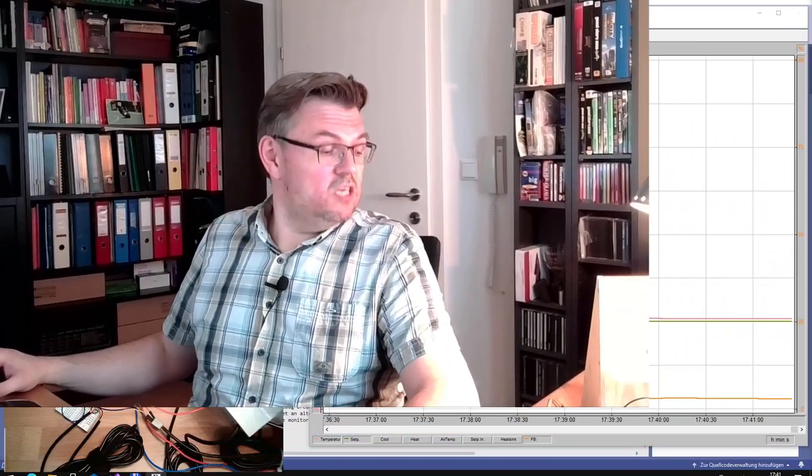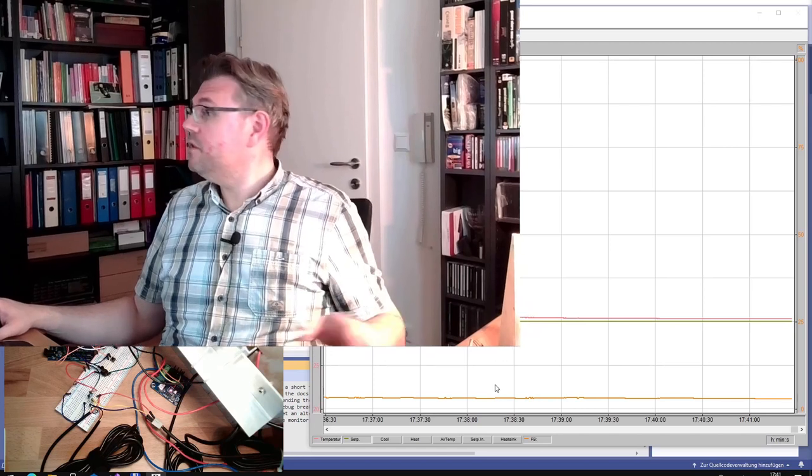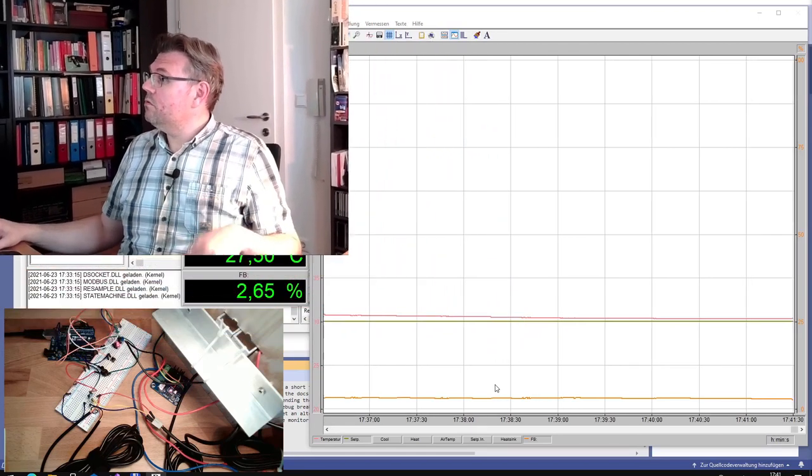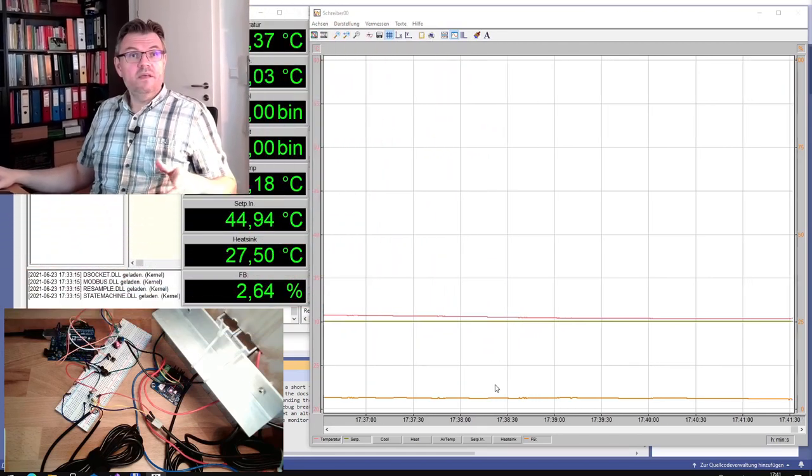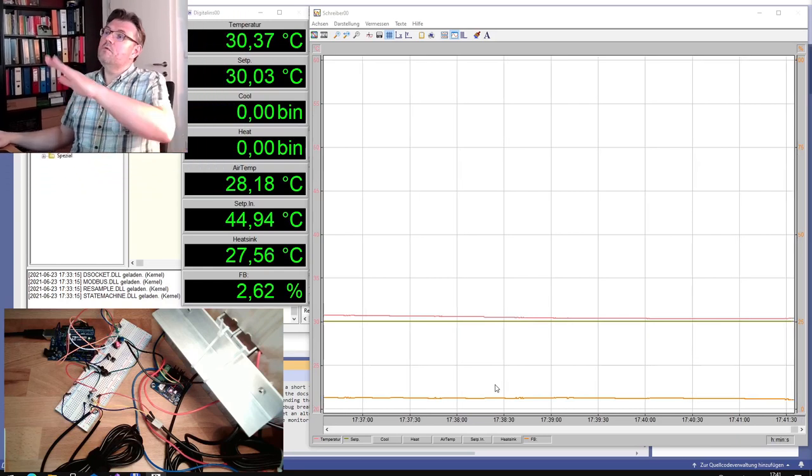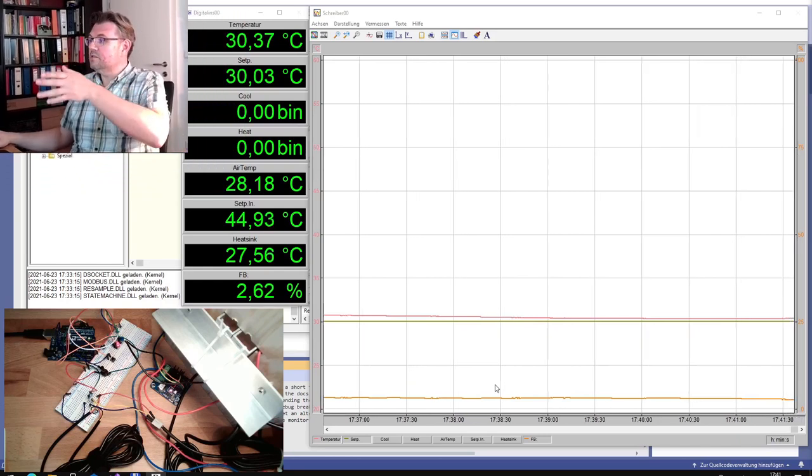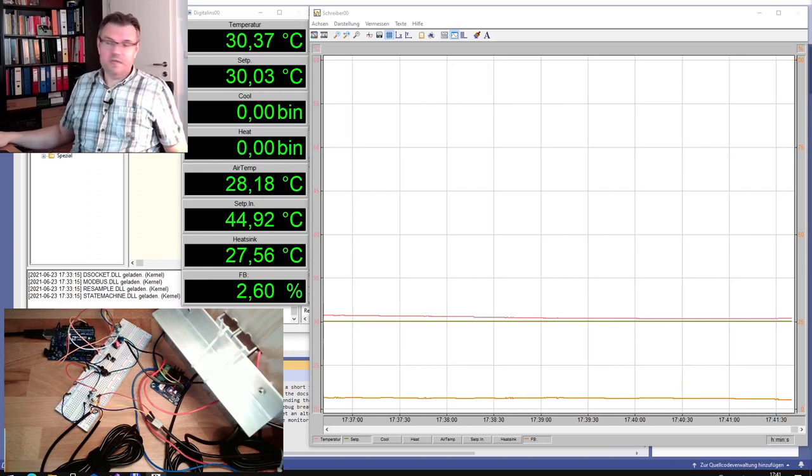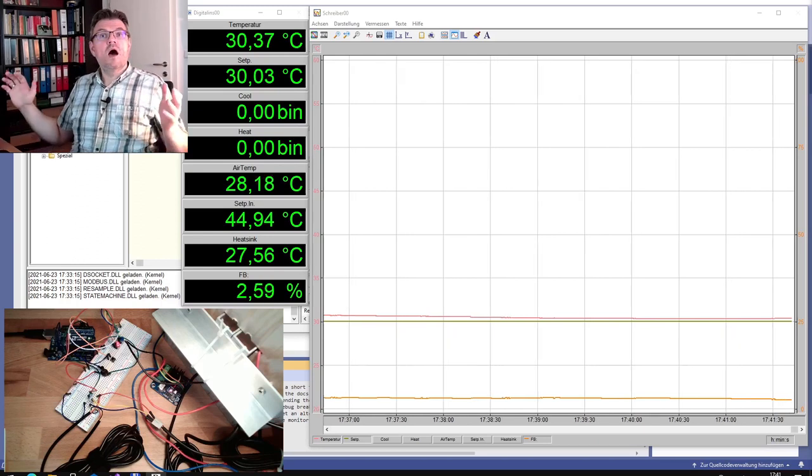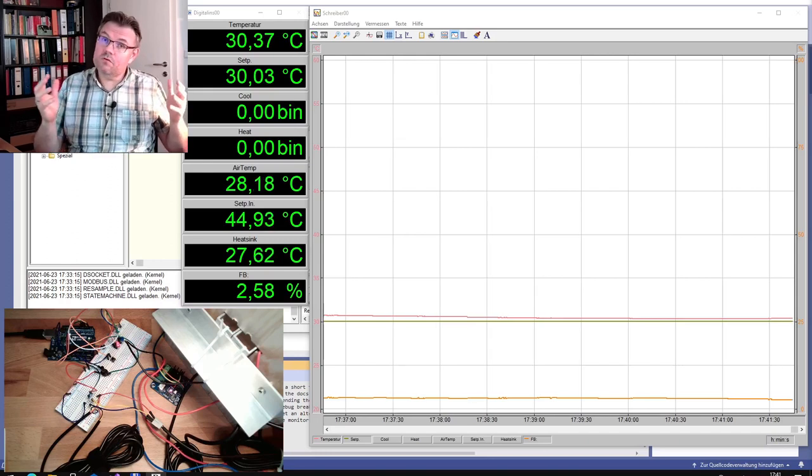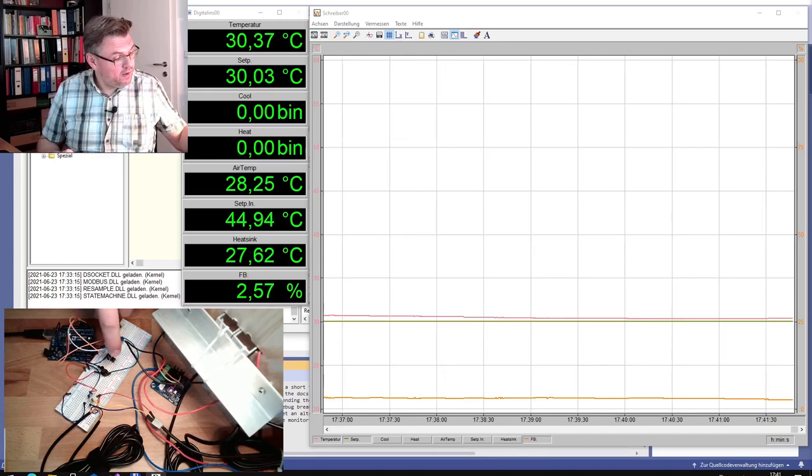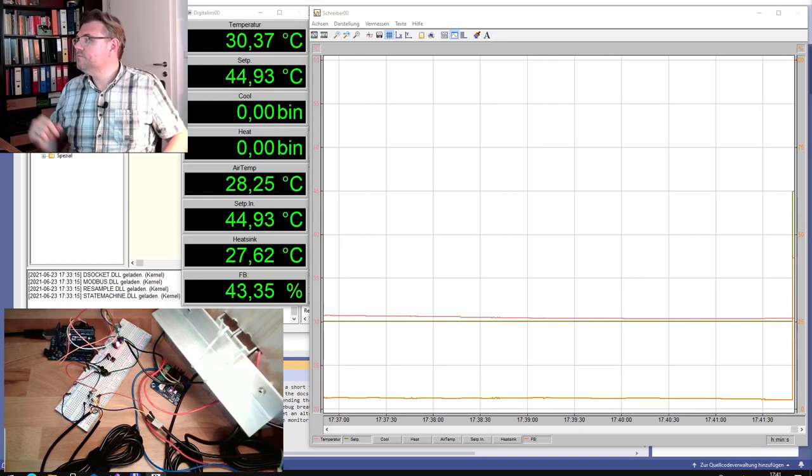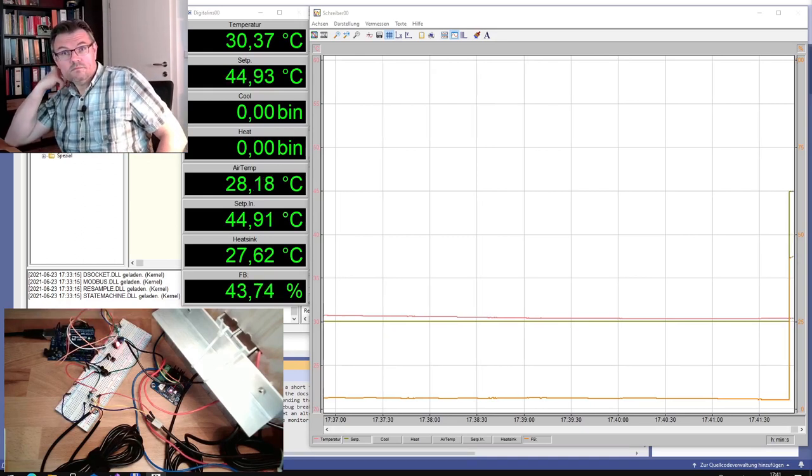So everything is set. PI controller is set to the corresponding parameters we just found out. K to 1.36 and TN to 145. Currently we are running at around 30 degrees Celsius. And I am going to trigger the setpoint now. Let's see. So trigger.